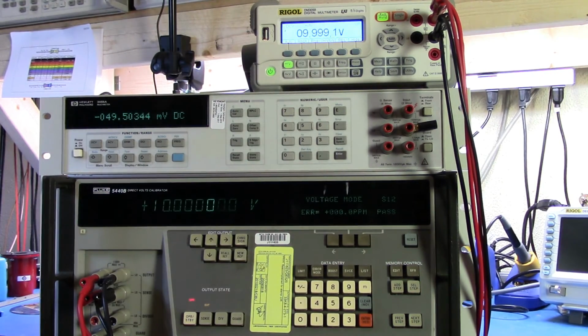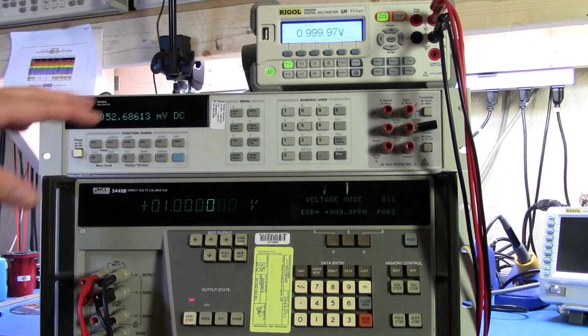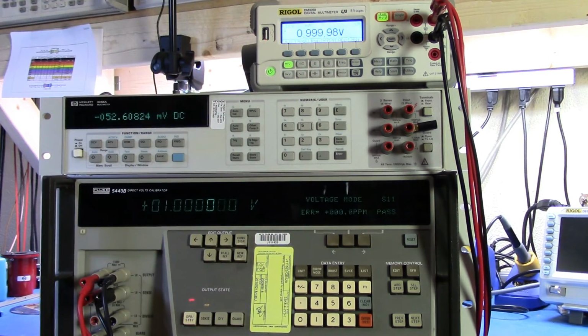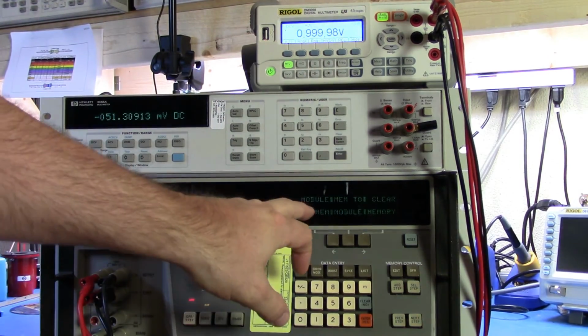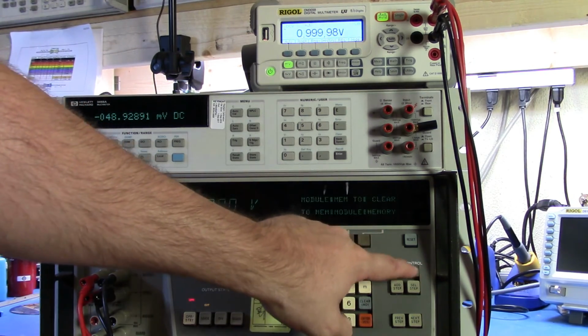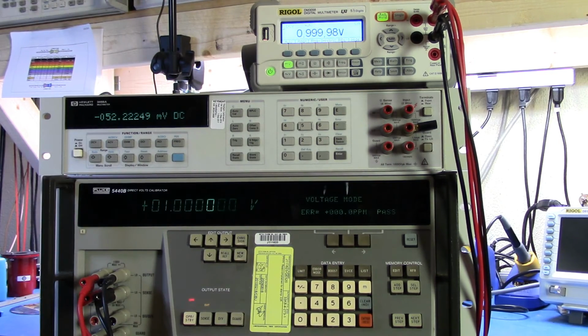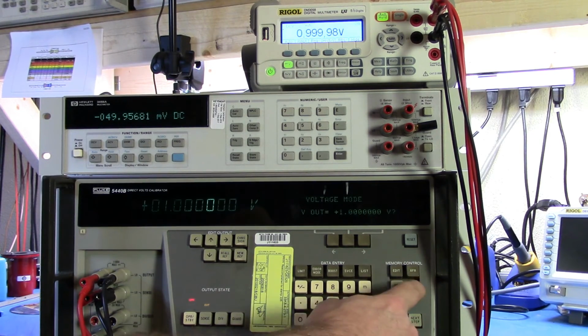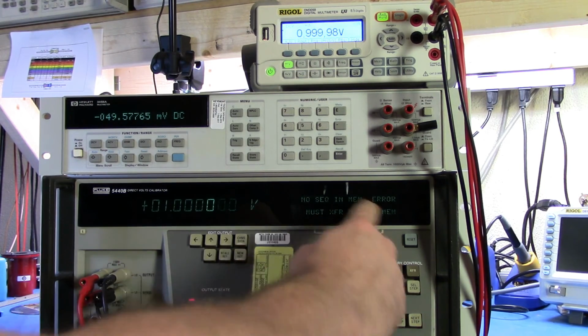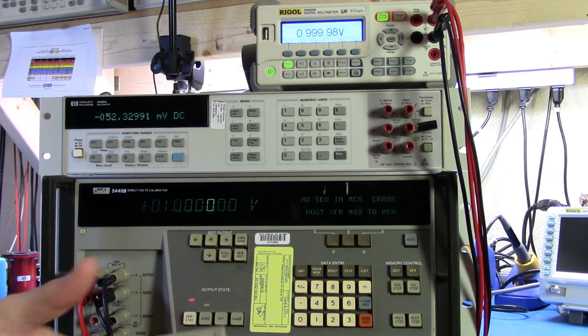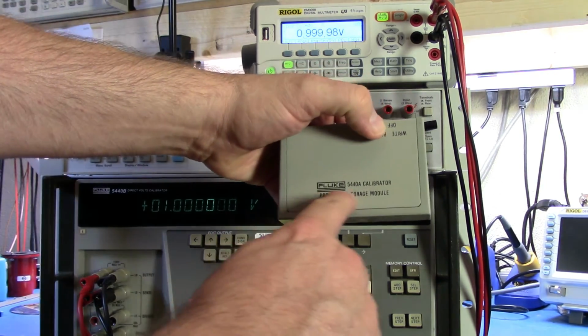Later on, I can come back and select step 11, which was the one that I just put in, and you'll see that it resets the value here and resets the unit. So I can quickly set up a set of tests that I want for my unit, and then save these to the memory module. Let me clear the memory right now, and if I select step, you'll see there's no sequence in there.